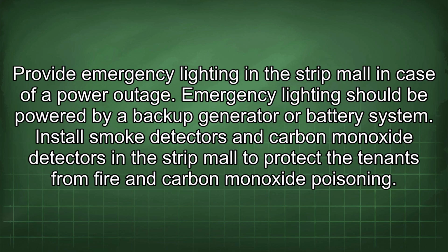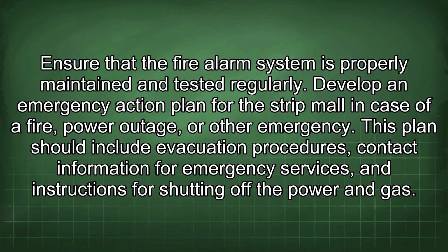Provide emergency lighting in the strip mall in case of a power outage. Emergency lighting should be powered by a backup generator or battery system. Install smoke detectors and carbon monoxide detectors in the strip mall to protect the tenants from fire and carbon monoxide poisoning. Ensure that the fire alarm system is properly maintained and tested regularly.